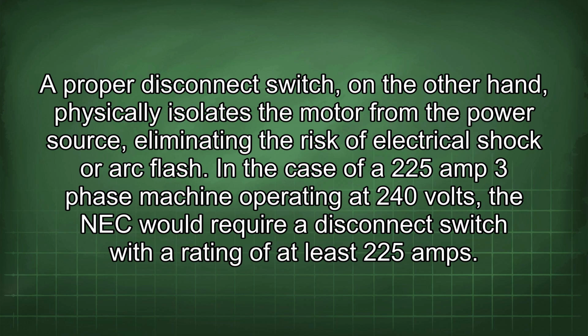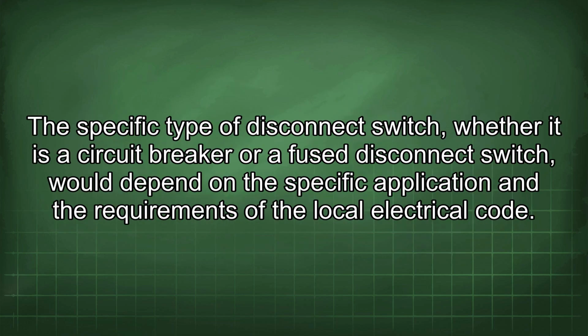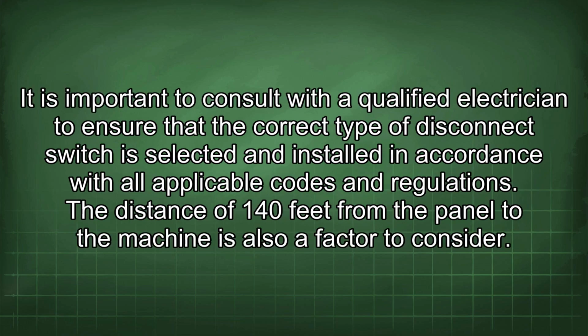In the case of a 225 amp three-phase machine operating at 240 volts, the NEC would require a disconnect switch with a rating of at least 225 amps. The specific type of disconnect switch, whether it is a circuit breaker or a fused disconnect switch, would depend on the specific application and the requirements of the local electrical code. It is important to consult with a qualified electrician to ensure that the correct type of disconnect switch is selected and installed in accordance with all applicable codes and regulations.